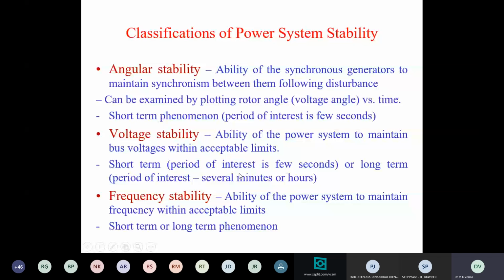Generally, voltage instability has been found to occur due to increase in demand. With a slow and gradual increase in demand, voltage goes on dipping, and finally a point comes beyond which you cannot load the system. To try to load the system further, there may be instability, and then voltage may go on sinking, and that may cause ultimately a collapse if it is not controlled. So generally it is a long-term phenomenon, but sometimes it may also be a short-term phenomenon.